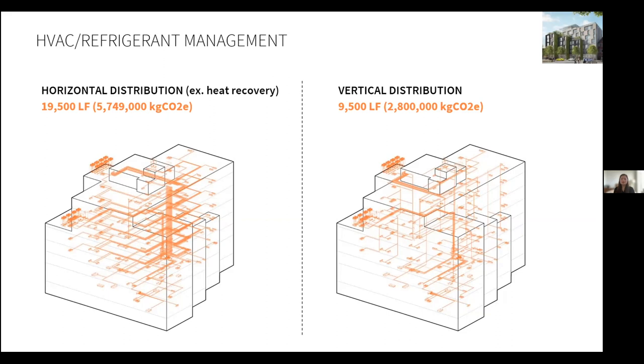In the vertical VRF system on the right, we would zone by facades to accommodate the temperature swings during the spring and fall seasons. We believe we can achieve the same level of comfort as the heat pump system, at the same time significantly reducing the amount of refrigerant lines for our building.